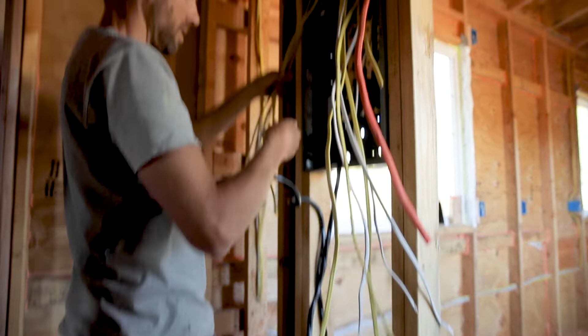So first thing we're going to do is screw in our ground bar. Now for a main panel that's connected directly to the power company, you can just put your ground wires with the neutrals. But because this is called a sub panel, because it's not hooked up to the power company, it's hooked up to another panel with its own breaker, the grounds have to be on their own bar. So these always come separate. Sometimes you need to buy them. This one came with the panel, but you need to attach it on because sometimes you don't use it. So when you do need it like this, you have to screw it on. So we're just gonna pick a spot like up here.